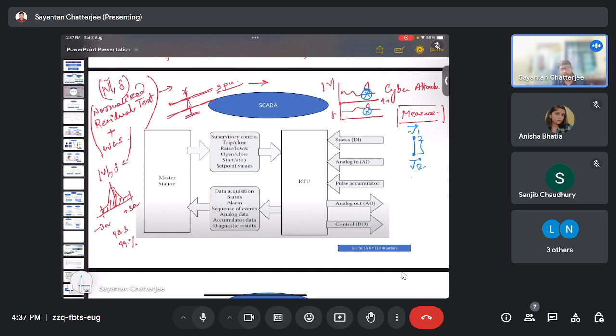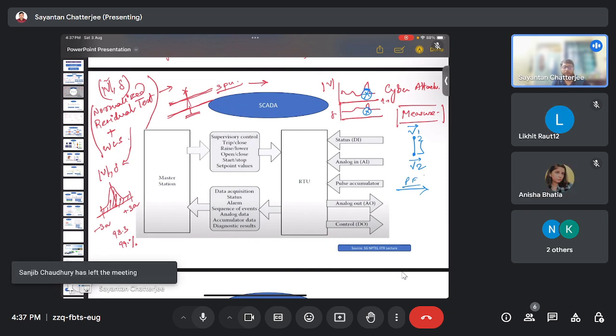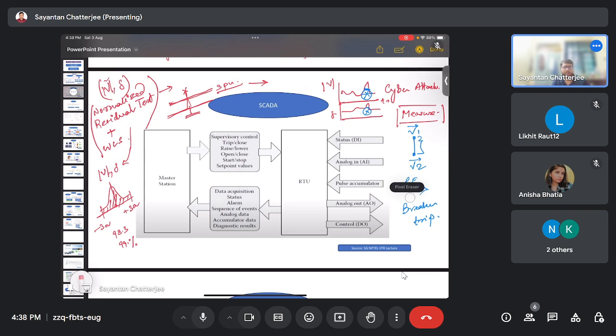This is entirely an automated thing. After the entire procedure, the power flows and all these things are calculated, and if it is found that the limits are violated, the breaker would trip, and it is tripping although it is in a healthy operating condition. That leads to a very problematic situation, and that would lead to some cascading failures. So that's the issue where we need to be careful while designing these estimators.